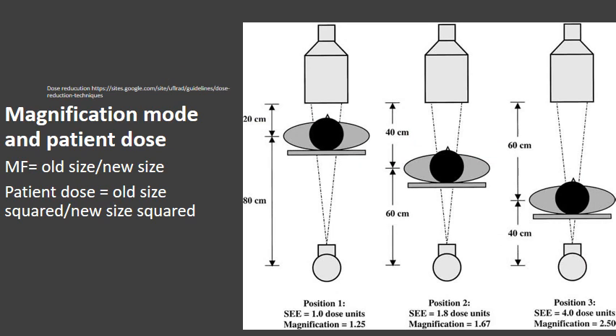So most systems have at least 3 and sometimes as many as 5 electronic magnification modes. And each, of course, has its own unique dose level because an increase of magnification increases dose. So when we're trying to figure out what the dose is, the rule of thumb is that the radiation dose to the patient increases by the square of the ratio of the image intensifier diameters. For example, if the entrance skin exposure is 100 units for a 23 centimeter field of view, the radiation entrance dose increases to 235 units when the field of view is reduced to 15 centimeters.